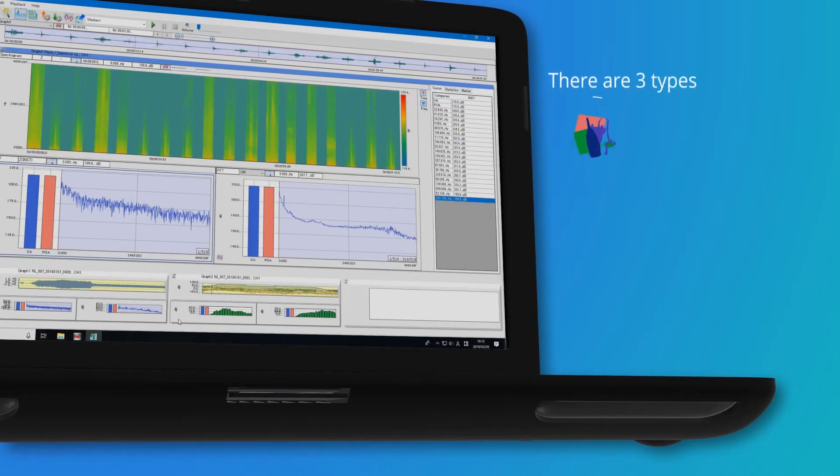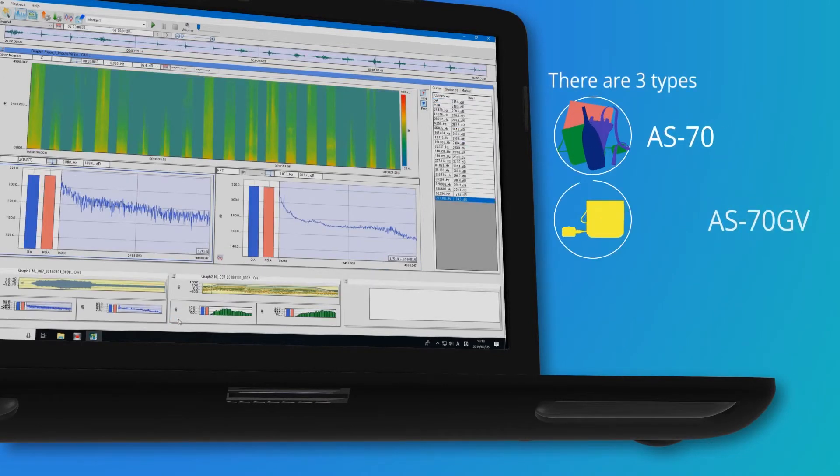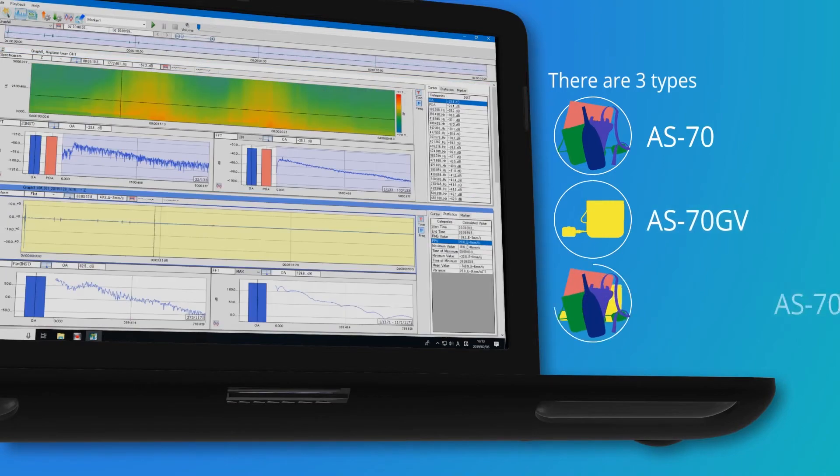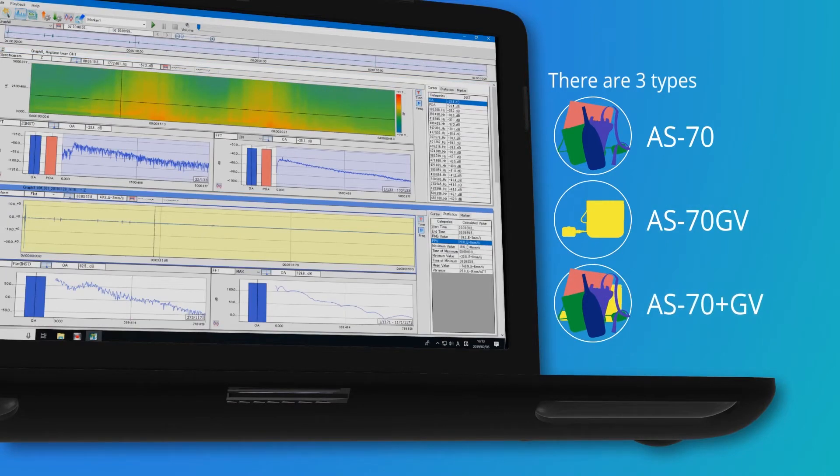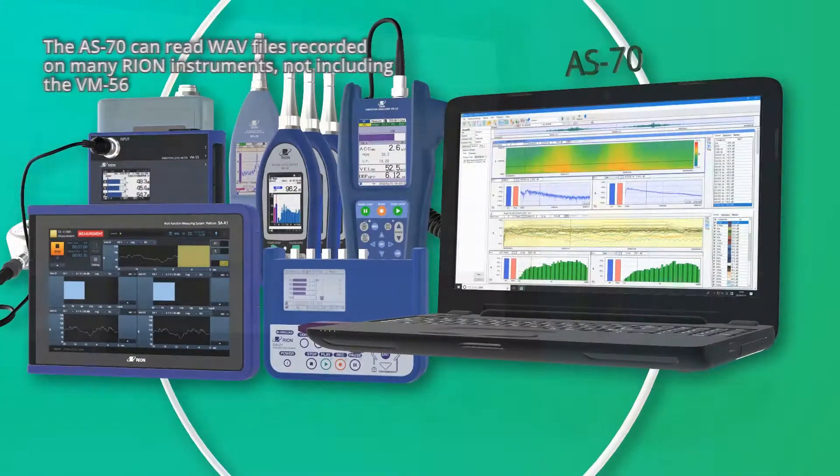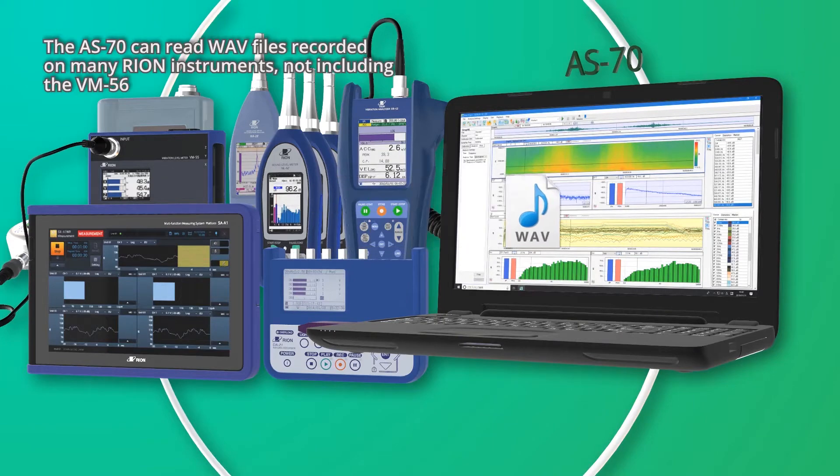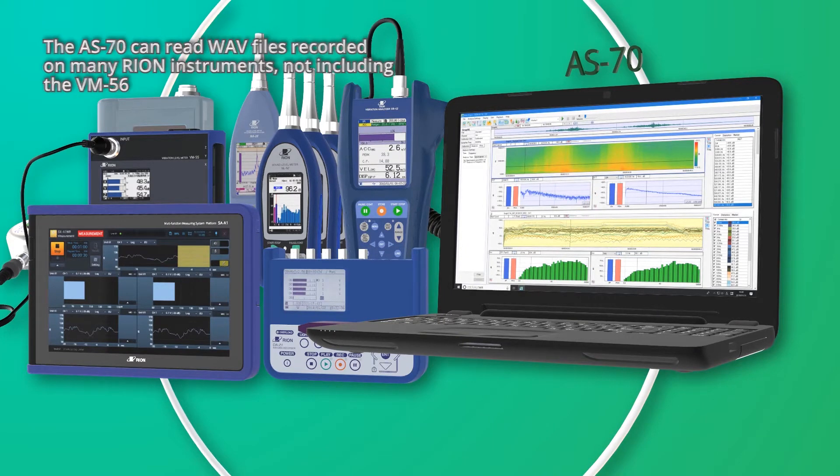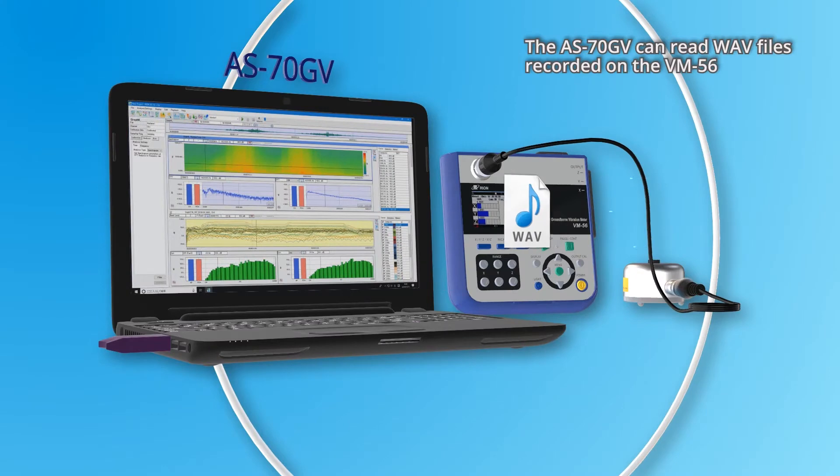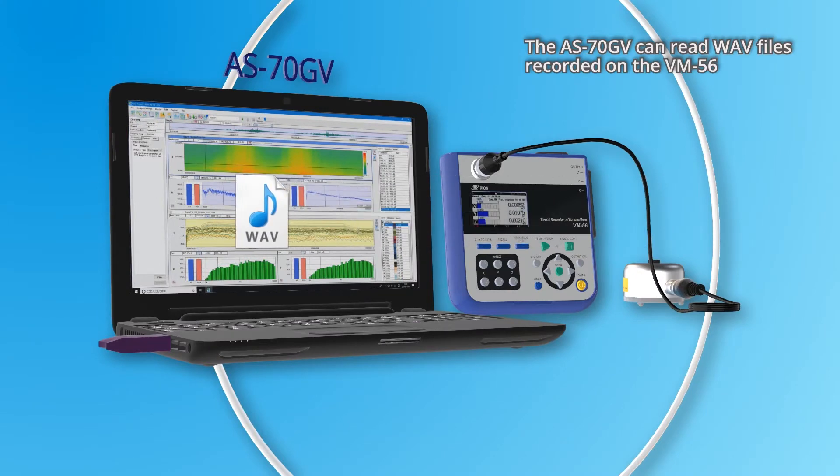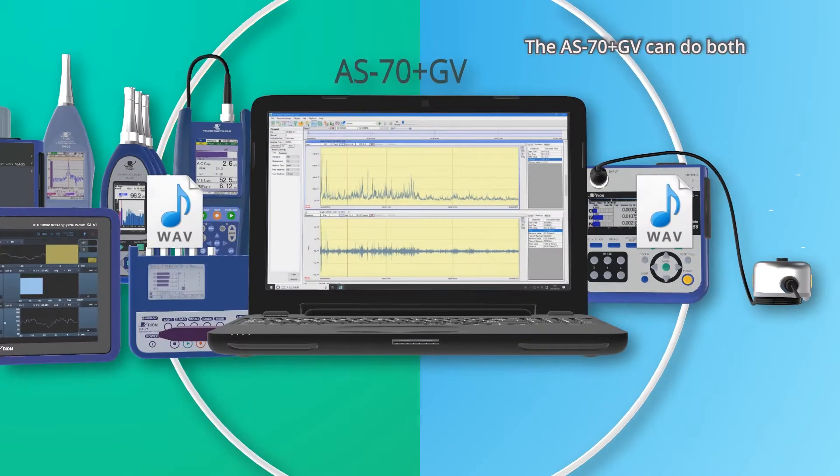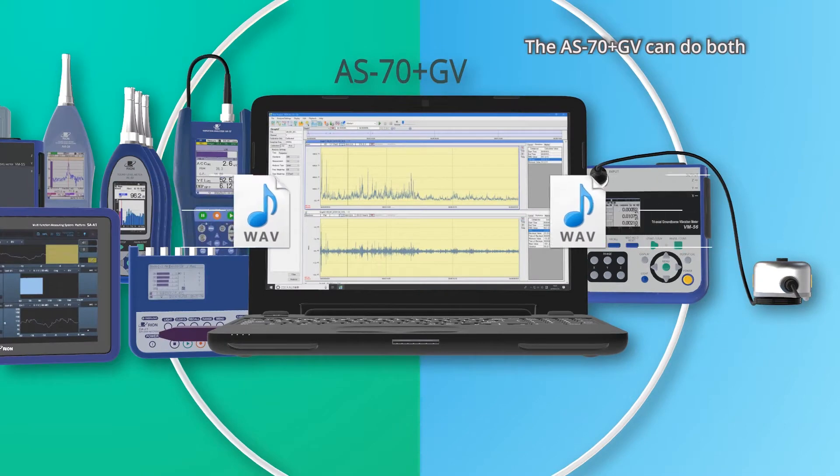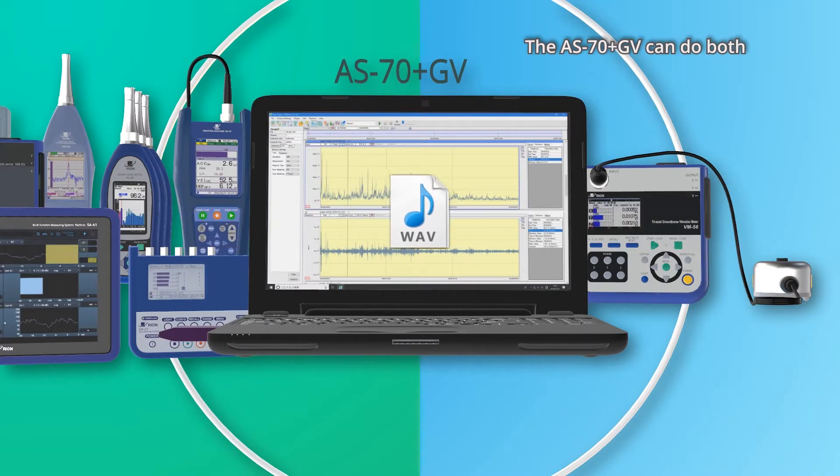There are three types: the AS-70, AS-70GV, and AS-70 PlusGV. The AS-70 can read WAV files recorded on many RION instruments, not including the VM56. The AS-70GV can read WAV files recorded on the VM56. The AS-70 PlusGV can do both.